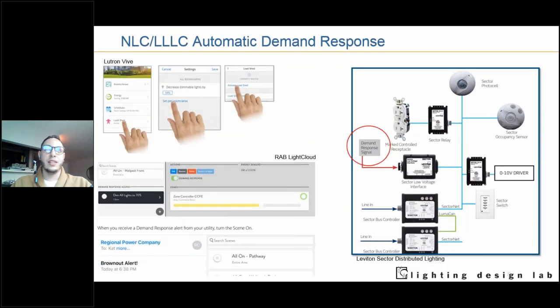Here are some screenshots from different systems showing what this could look like - activate the load shed, have everything dimmed down by 34%, activate it. You can have, for example, the system from RAB LightCloud, they'll send an email, and you can activate demand response through an email as well. If you don't have a phone or tablet-based application, you can have a demand response signal - you send a contact closure to load controllers, and the system can then respond by turning off or dimming down load in itself.